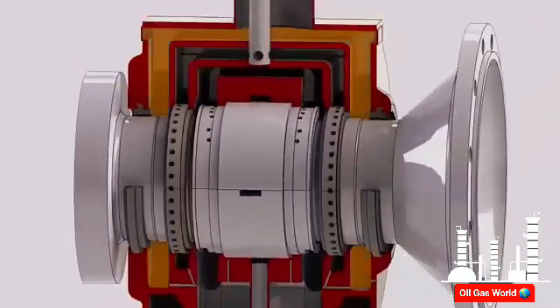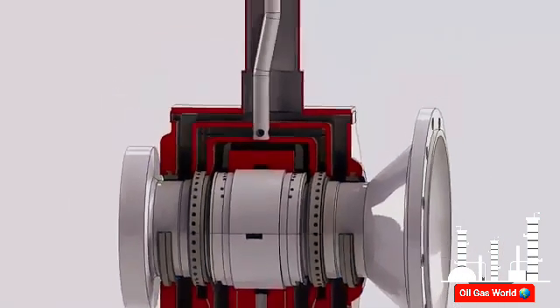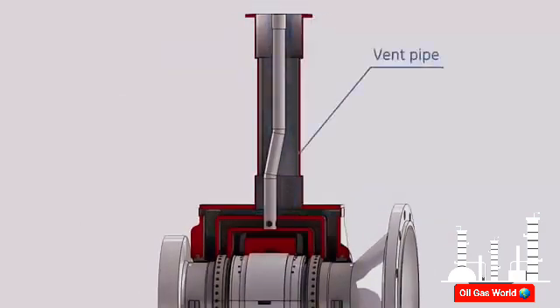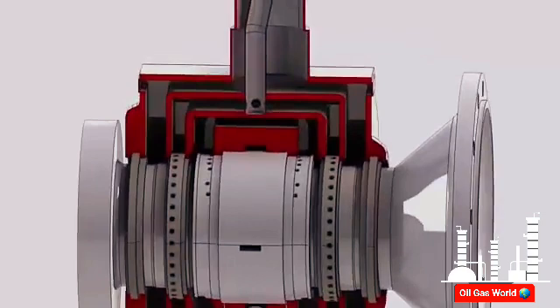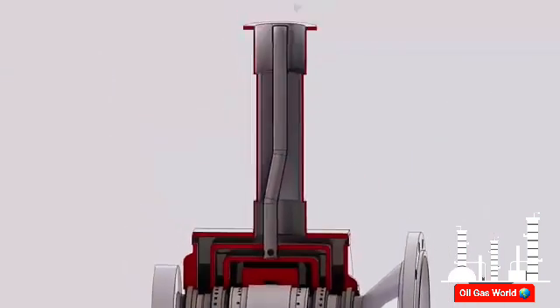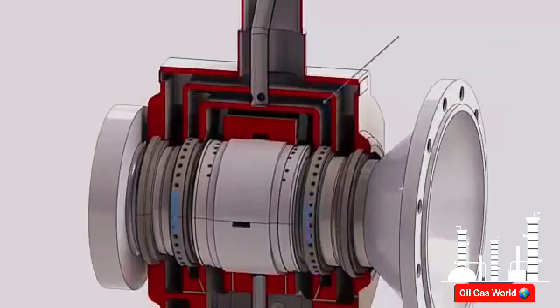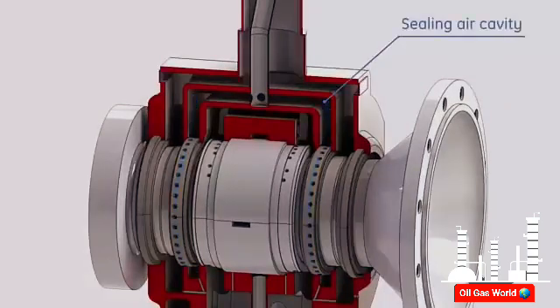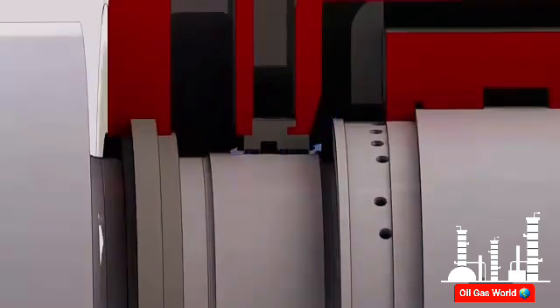A brush seal is installed on both labyrinth seals to minimize air leakage as much as possible. Bearing 2 has a vented cavity. The compressed air leaking from the outer labyrinth seals is vented to the atmosphere through a vent pipe mounted on the top of the housing. Inboard of the outer air seals, two pressurized labyrinth seals are located for lubricant control. Sealing air supplied through a pipe concentric with the vent pipe fills the sealing air cavity and flows between the two rows of each of the labyrinth seals.